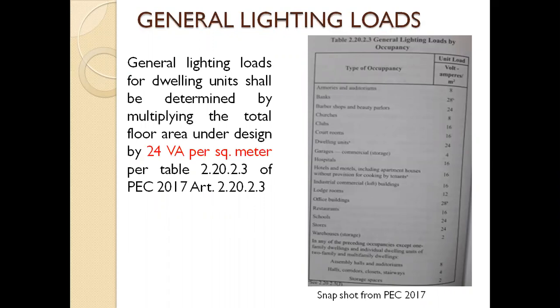So, general lighting loads. General lighting loads for dwelling units shall be determined by multiplying the total floor area under design by 24 volt-ampere per square meter. Based on PEC 2017 Table 2.20.3 under general lighting loads by occupancy, dwelling units are 24 volt-ampere per square meter. This is the unit load, the criteria for sizing the general lighting loads for dwelling units.